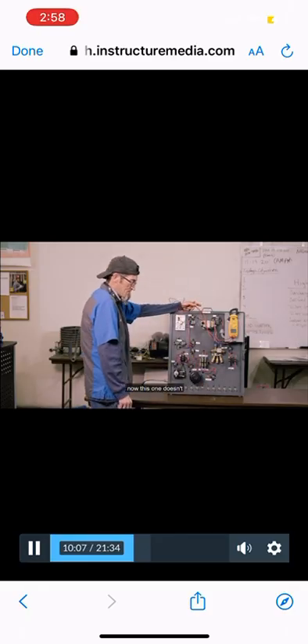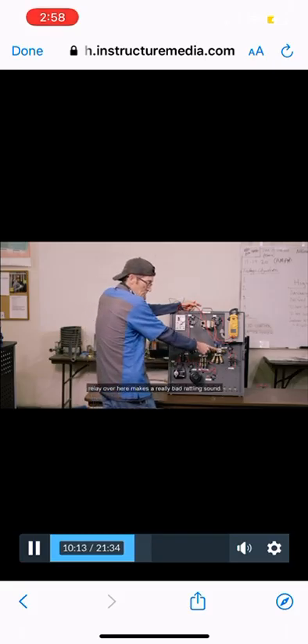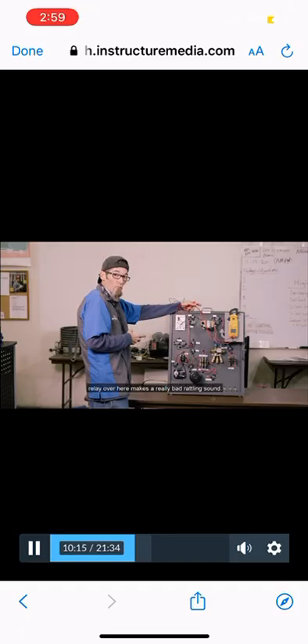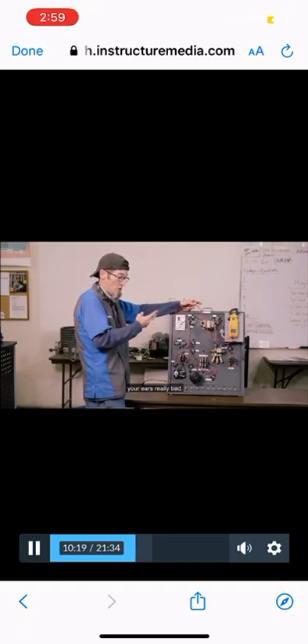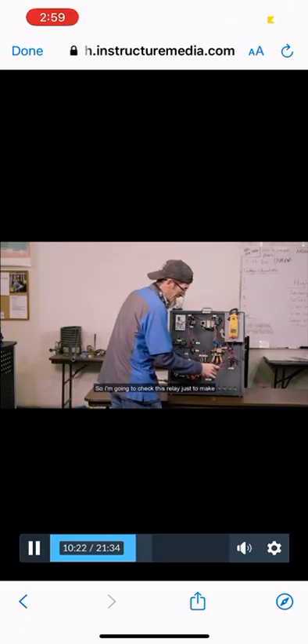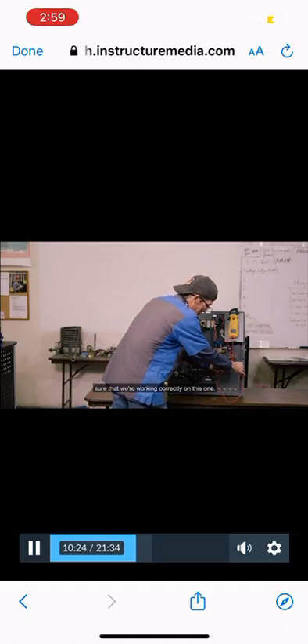Okay, now this one doesn't look like anything's really changed. So the only thing I'm going to do is, normally this relay over here makes a really bad rattling sound. It's called a reversing valve. I disconnected it because it would be like ringing in your ears really bad. So I'm going to check its relay just to make sure that we're working correctly on this one.